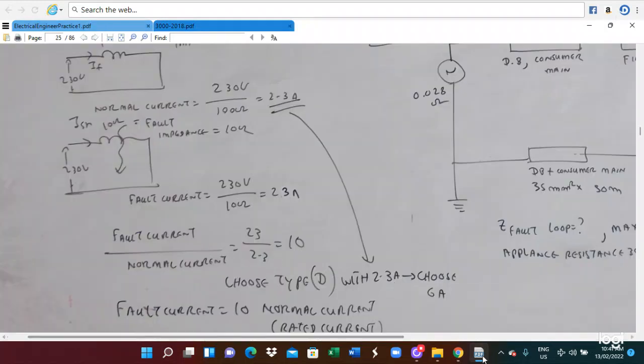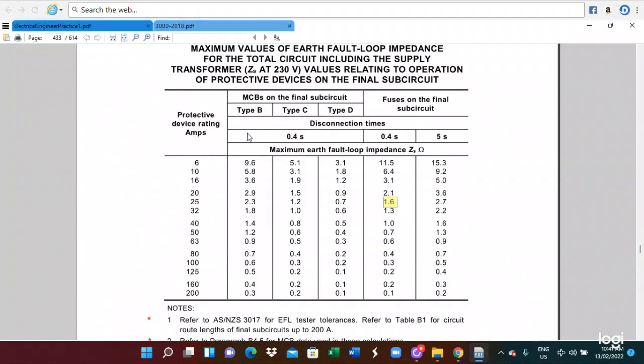For 2.3, you can see in the AS3000 rules, table 8.1, there is no 2.3 ampere; the minimum is 6. So for the type D circuit breaker, the protective rating has no 2.3, only 6 is available. So you utilize a type D circuit breaker, and the maximum impedance is 3.10. This is the way we find the impedance.